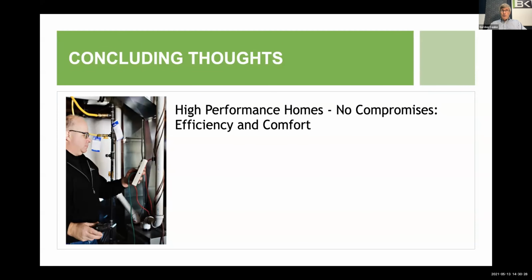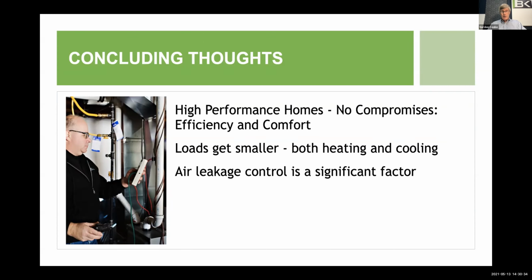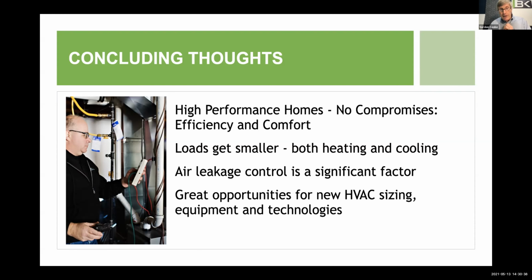So in the high performance houses, no compromise. Efficiency and comfort. You're going to have to go a little further. The loads get smaller, both heating and cooling. Air leakage, of course, is a significant factor, but great opportunities for new HVAC sizing. Your savings come from the size of the air conditioner and the size of the ductwork. That's where the savings come from in terms of capital cost. It also saves you because of fewer warranty callbacks because of comfort. Commission your systems. Hopefully that was useful.